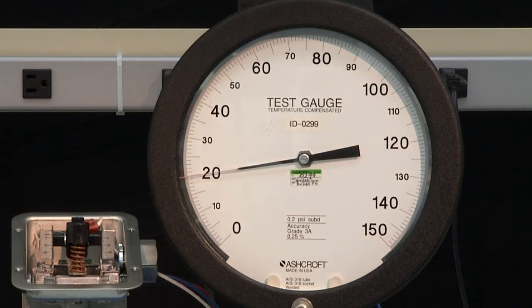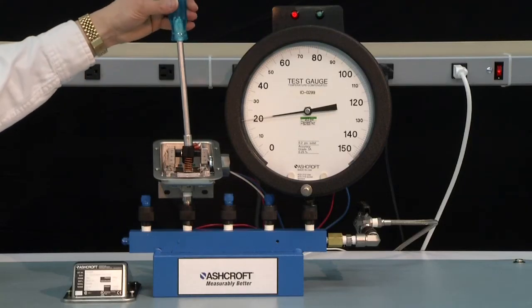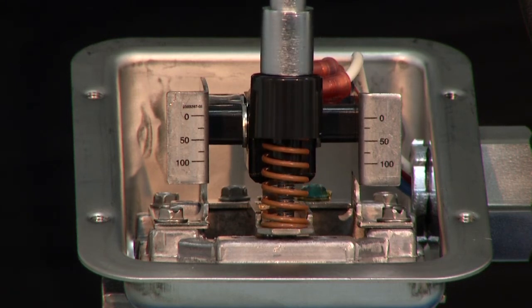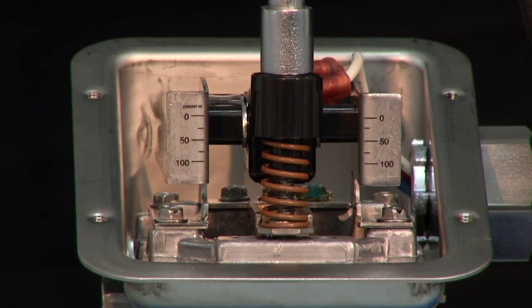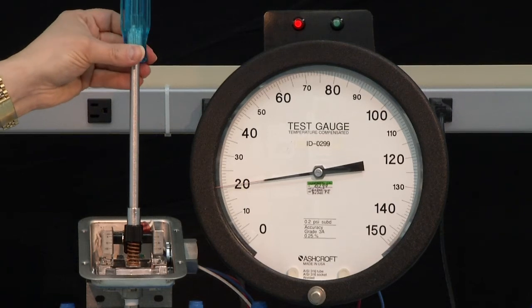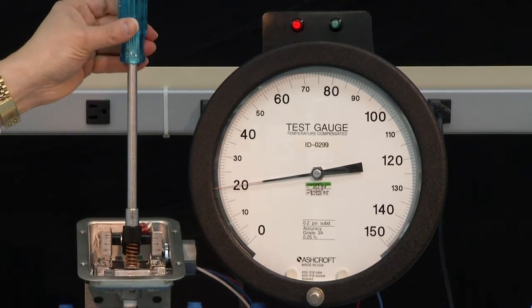With the pressure of 20 pounds we are now going to turn the adjustment knob counterclockwise or raising it up to lower the set point of the switch. We're going to keep going counterclockwise until we have the light turn on.